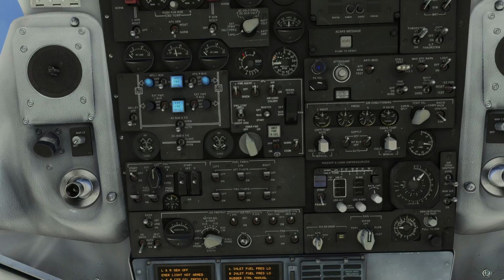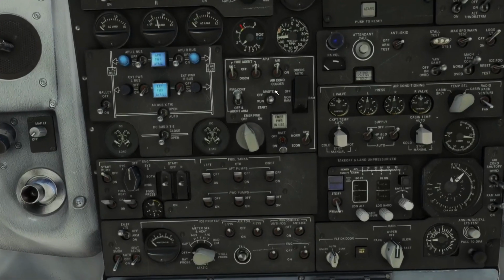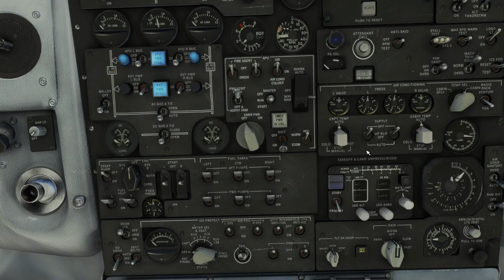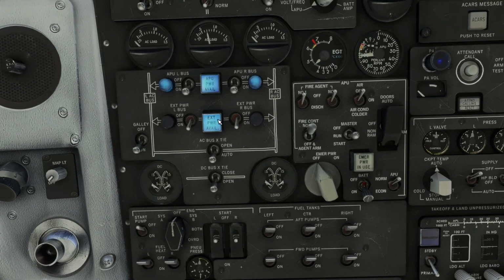Once it's on and running, it actually takes a lot less power to keep the electrical motor running. They have a lot more starter current than when they're just running normally. Same thing with these guys, because there are a lot of fans kicking on with the packs, so the initial current draw is so high you'll see this gauge jump and then jump back. You want to make sure you don't kick them on at the same time or you can have problems. So again, wait a minute before you do the air, then put the packs on one at a time, let it stabilize, then put the next one on to protect your electrical system.